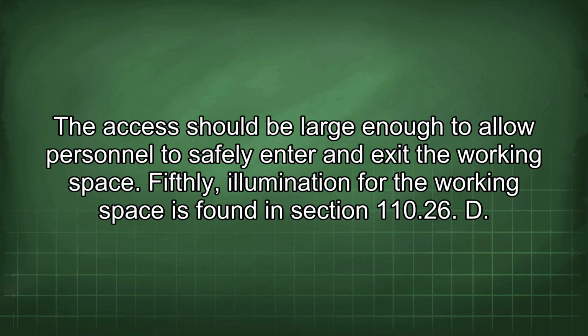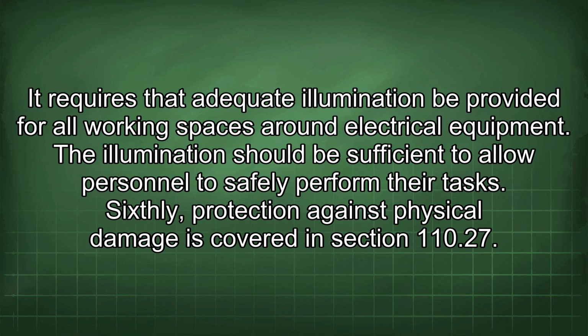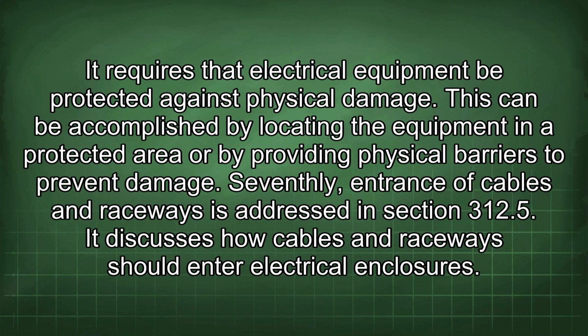Fifthly, illumination for the working space is found in Section 110.26 D. It requires that adequate illumination be provided for all working spaces around electrical equipment. The illumination should be sufficient to allow personnel to safely perform their tasks. Sixthly, protection against physical damage is covered in Section 110.27. It requires that electrical equipment be protected against physical damage. This can be accomplished by locating the equipment in a protected area or by providing physical barriers to prevent damage.